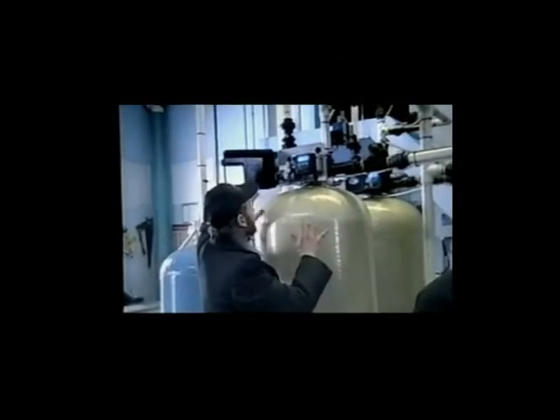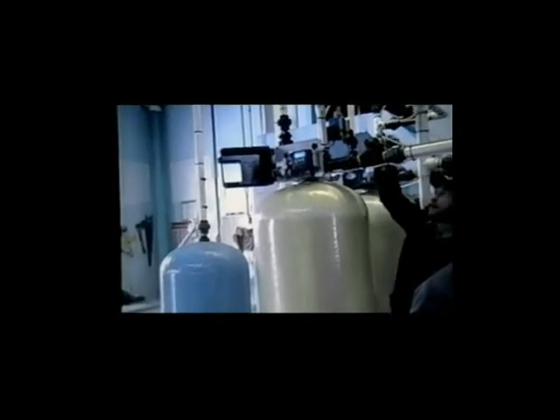Now I'm using air — set a gauge up there about 20 PSI more. We're going to need a regulator. So it opens this valve, and there's air going to those two valves. It gives air — air comes in here and also here. This is a normally open valve, this is a normally closed valve. So when you apply air to it, this normally open valve closes, and the normally closed valve opens.